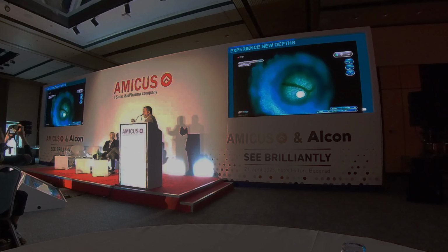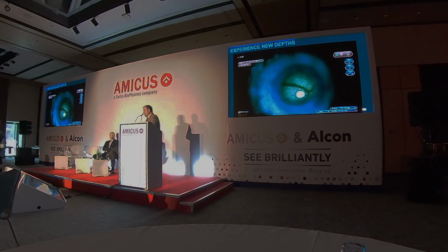I don't know if you are aware, but there is a difference between the stereo base of Möller-Wedel, Zeiss, and Leica. Alcon and Zeiss share a similar stereo base, meaning the pathway of the optics. And the Ngenuity camera, albeit highly versatile, you can put it on every type of microscope, works best with Alcon Zeiss microscopes because the sensors are perfectly aligned with the visual axis of the microscope. So have that in mind.